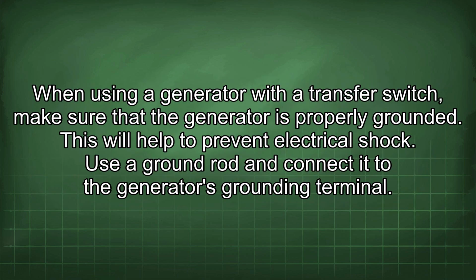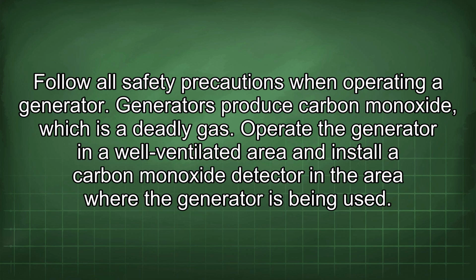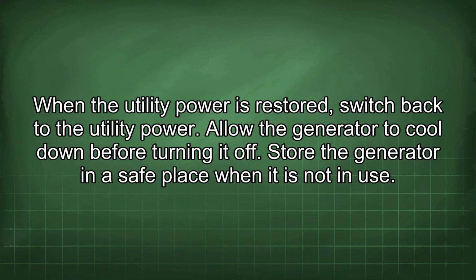When using a generator with a transfer switch, make sure that the generator is properly grounded. This will help to prevent electrical shock. Use the ground rod and connect it to the generator's grounding terminal. Follow all safety precautions when operating a generator. Generators produce carbon monoxide, which is a deadly gas. Operate the generator in a well-ventilated area and install a carbon monoxide detector in the area where the generator is being used. When the utility power is restored, switch back to the utility power.